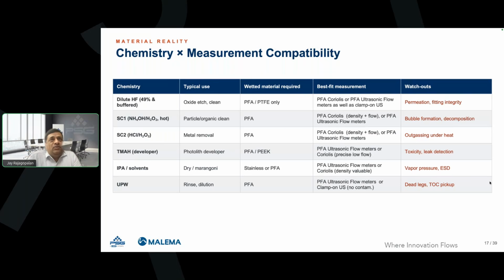Dilute hydrofluoric acid, obviously, is extremely aggressive, as we know, and it's used in oxide etch and clean applications. PFA and PTFE are the only choice, PFA more so than PTFE in the flow, especially constrained flow. Ultrasonic and Coriolis flow meters and flow controllers can be applied here. Permeation is definitely a concern. With an inappropriate thickness of the PFA tube, or areas where there is a very thin layer of PFA rather than a thick one, hydrofluoric acid gases can permeate through, and that can lead to corrosion or an unsafe environment. In which case, people sometimes use a purge fitting on the devices to keep the pressure inside the unit elevated, such that permeation is limited or non-present.